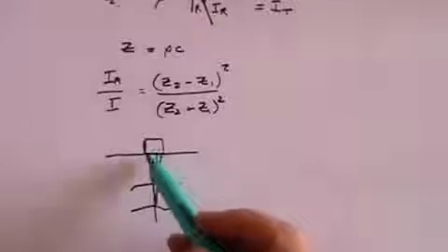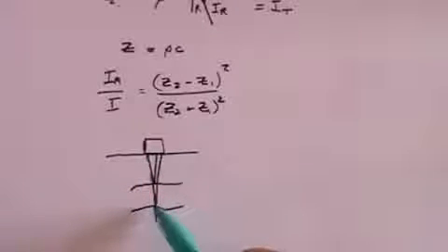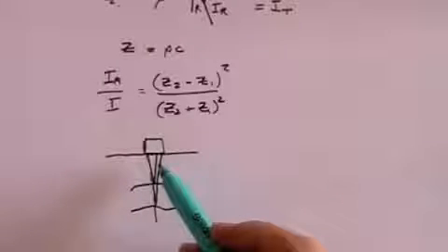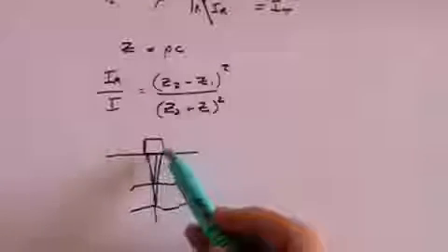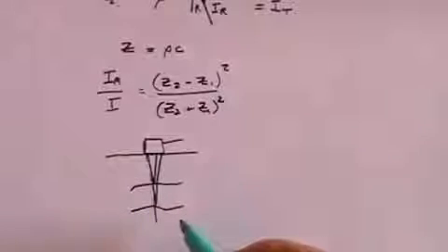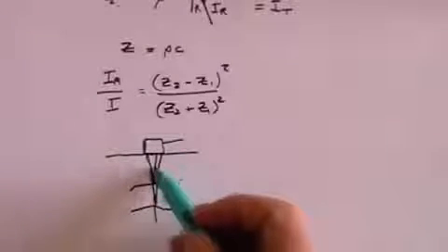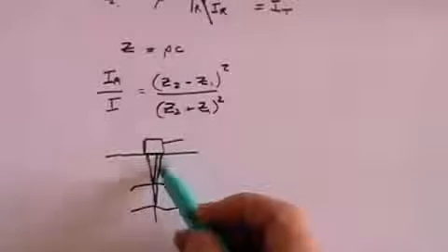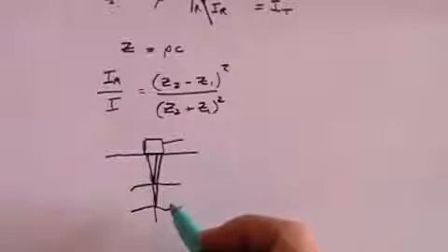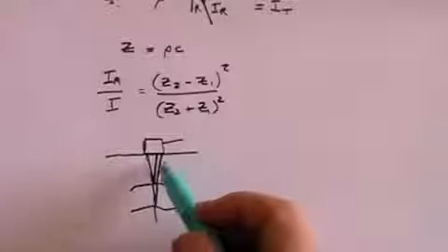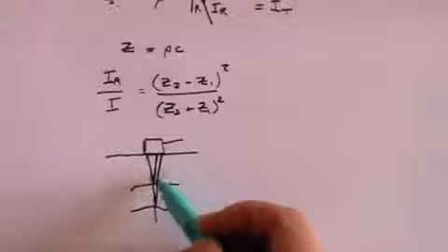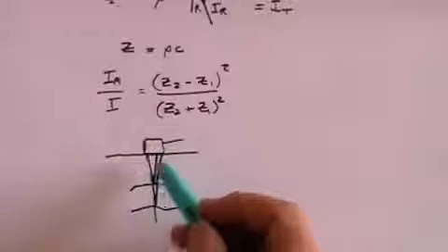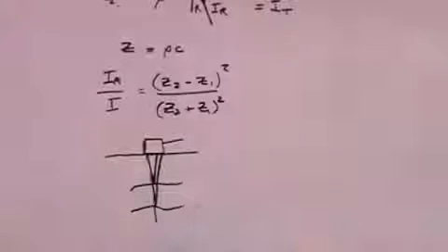Of course, you have to recognise that the further the sound pulse goes before it is reflected, the more likely it is to be attenuated, that is, to lose power. And so in this device, or in the electronics that follow it, you have to compensate for that, so that this signal coming from this boundary will be stronger than this signal coming from this boundary. And in order to get a proper picture, of course, you want those strengths to be the same. So this signal coming from this boundary will need to be amplified so that it's comparable in strength to the signal coming from that boundary.